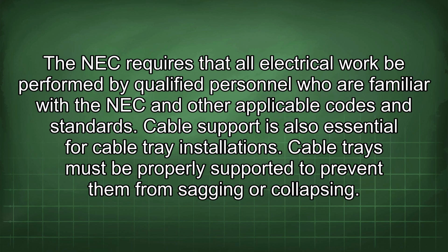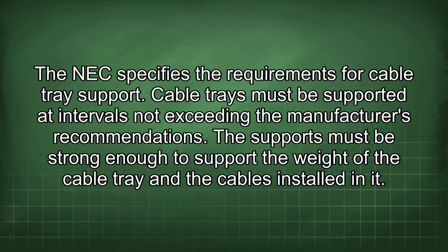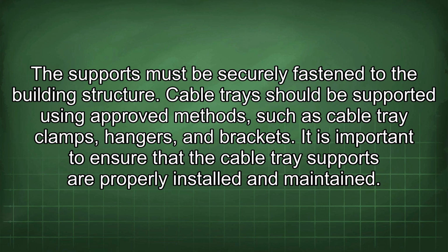Cable trays must be properly supported to prevent them from sagging or collapsing. The NEC specifies the requirements for cable tray support. Cable trays must be supported at intervals not exceeding the manufacturer's recommendations. The supports must be strong enough to support the weight of the cable tray and the cables installed in it. The supports must be securely fastened to the building structure. Cable trays should be supported using approved methods such as cable tray clamps, hangers, and brackets.